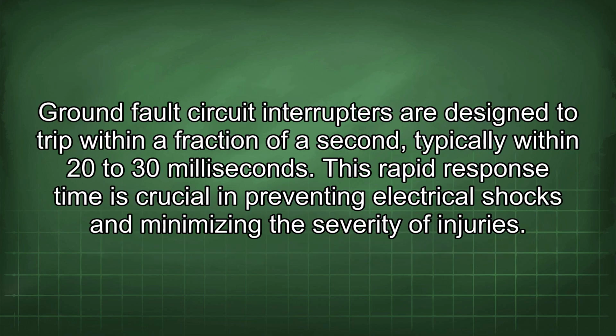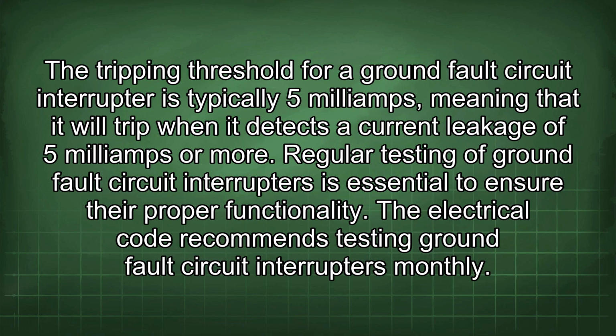Ground fault circuit interrupters are designed to trip within a fraction of a second, typically within 20 to 30 milliseconds. This rapid response time is crucial in preventing electrical shocks and minimizing the severity of injuries. The tripping threshold for a ground fault circuit interrupter is typically 5 mA, meaning that it will trip when it detects a current leakage of 5 mA or more. Regular testing of ground fault circuit interrupters is essential to ensure their proper functionality.